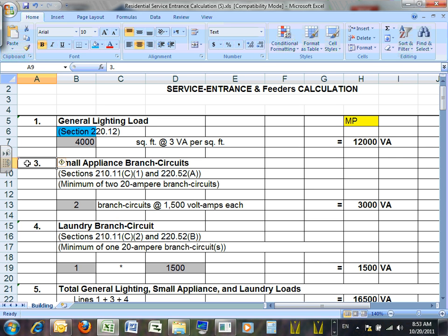You know what they use the branch circuit calculation for? You take the square foot of the building, divide it by the voltage, and divide it by 15 amp, and it gives you how many 15 amp circuits you need. The electrician does that. We are designers. I told you guys how we circuit. We don't circuit to the maximum, so we circuit based on no more than 10 outlets on one circuit. So I care less about the branch circuit calculation. Okay, step number 3. Any question guys about step number 1?